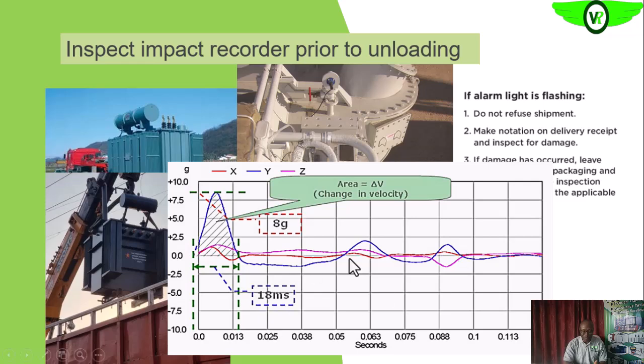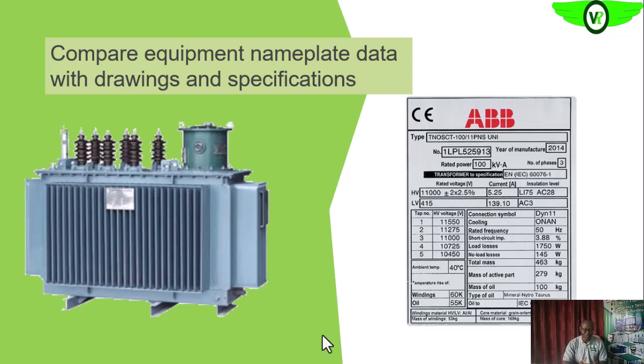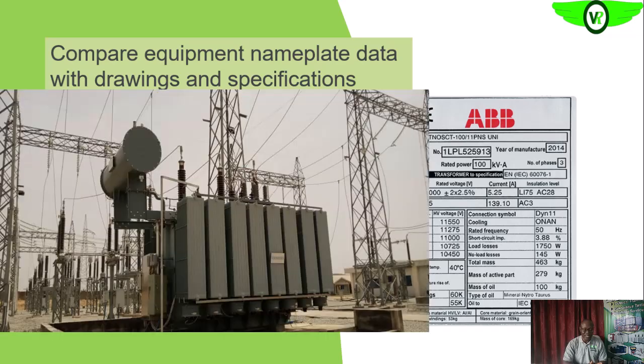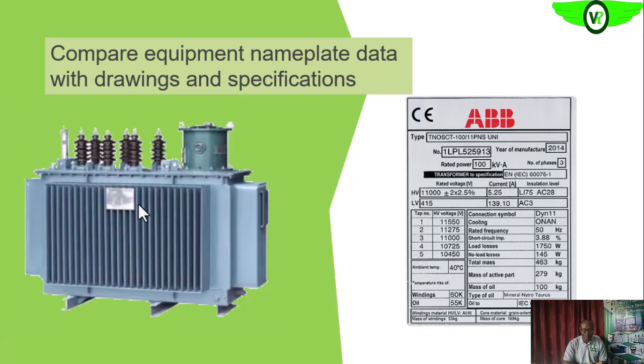So this is what you will see during your analysis. The degree of impact, that is the amplitude of the impact and the time of occurrence, will all be recorded. We'll analyze it to see that none of them is beyond the alarm limit. We'll then go ahead to look at the nameplate information to verify that what was specified and ordered is what is delivered. This we can also do on a transformer that has been installed already. We'll look at the nameplate and ascertain that what is specified is actually what is installed in the unit.